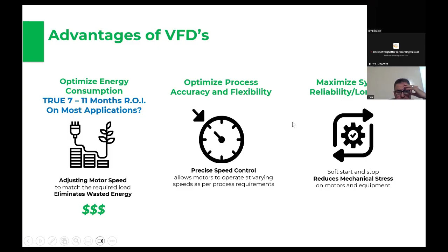Now, with the adjustable speed drives, as many of you may know, there's line side impacts. So on the line side of the VFD, you get your harmonic distortion, and that causes problems upstream from the drive to the grid and so on. It also contributes to what we call common mode voltage on the back end. And of course, there are specifications, IEEE 519, that require that the total harmonic distortion be less than 5% or 8%, et cetera, depending on what your characteristics are for that application.